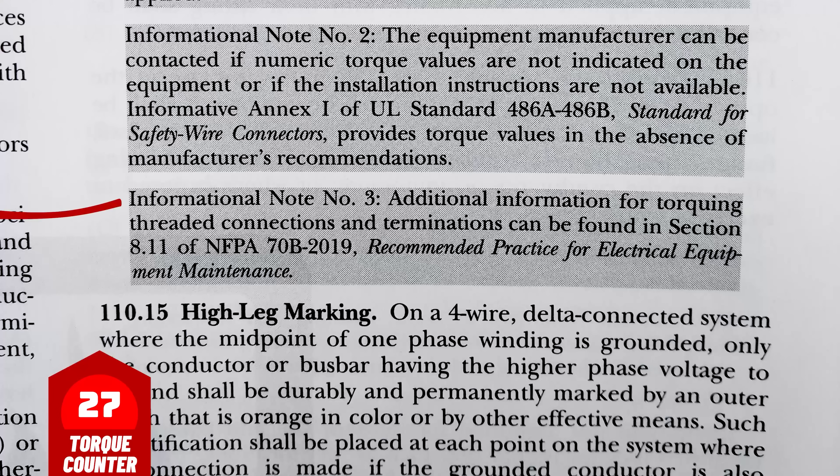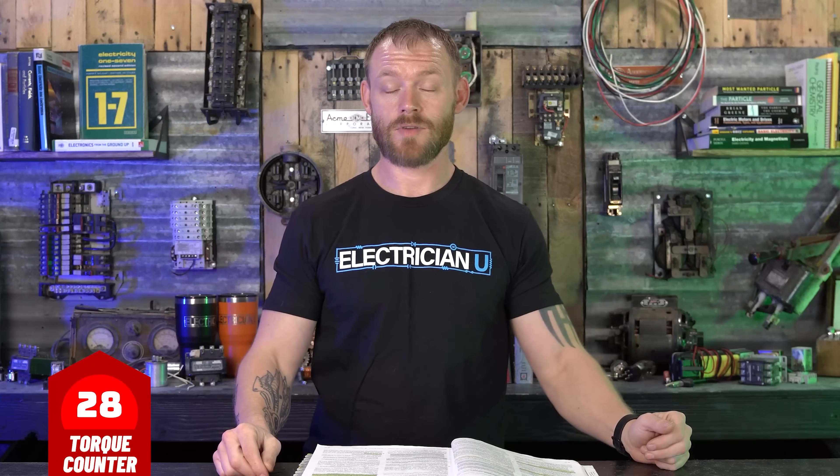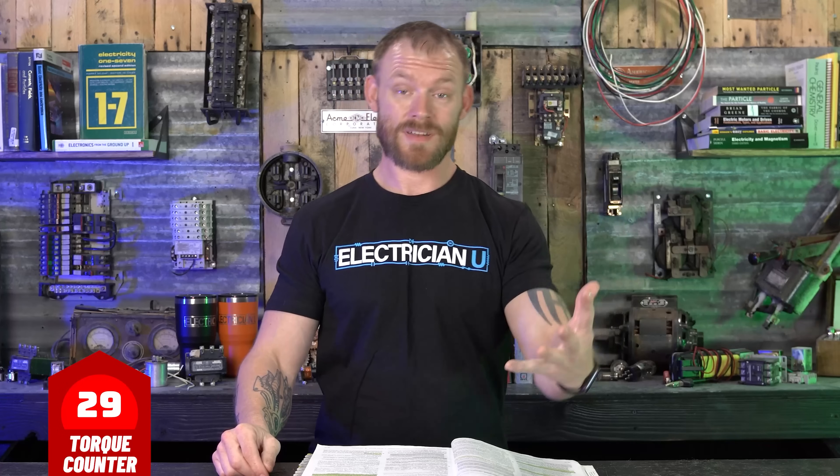Informational Note 3: additional information for torquing threaded connections and terminations can be found in Section 8.11 of NFPA 70B-2019, Recommended Practice for Electrical Equipment Maintenance. So that is everything. Nothing in there says you have to torque. It just says that equipment needs to have torque values on it, and that if it does — or if the instructions mention torque values — you need to use an approved means of torquing.